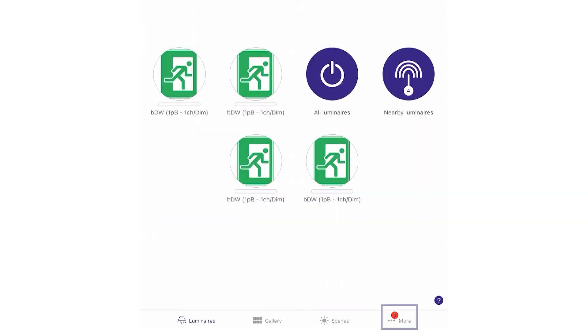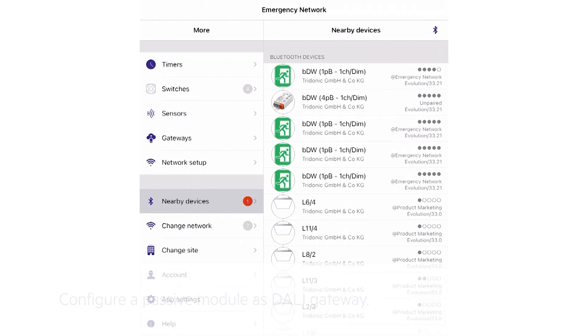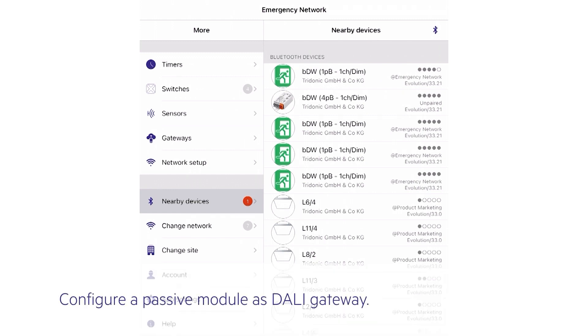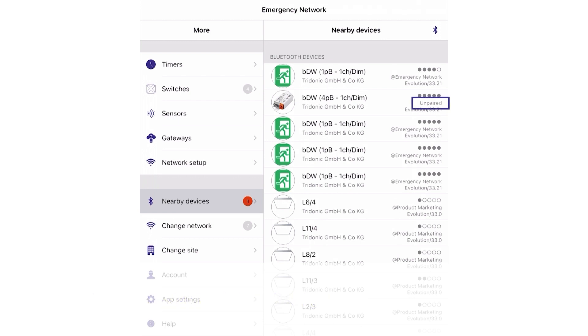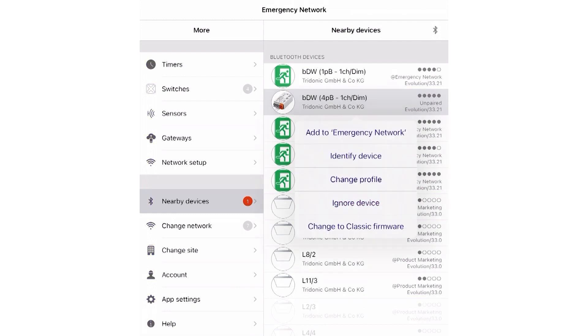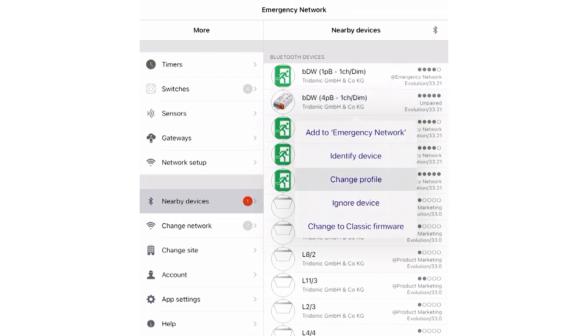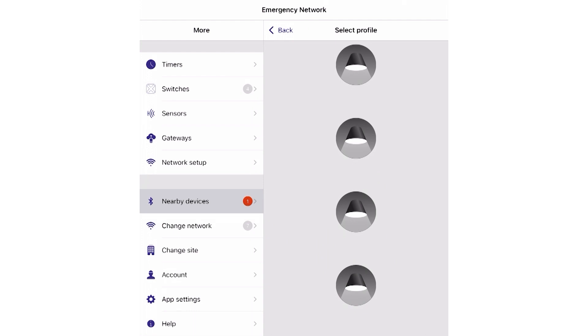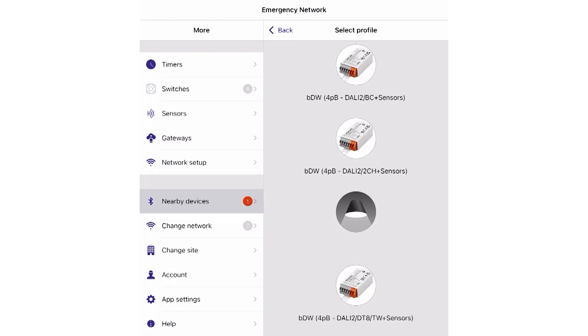In the second step, configure a passive module as DALI gateway. To do this, it's necessary to power an unpaired passive device. Brand new devices like in this example are already unpaired. After this is done, the device shows up in the nearby devices section of the app. Tap on this device and choose change profile. In the appearing list, select the DALI gateway profile.